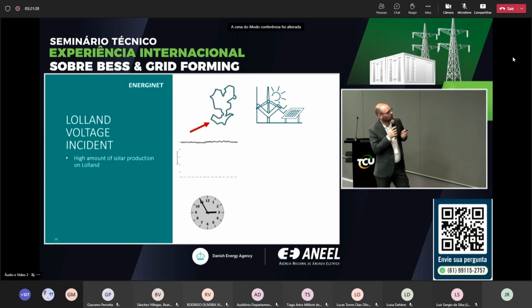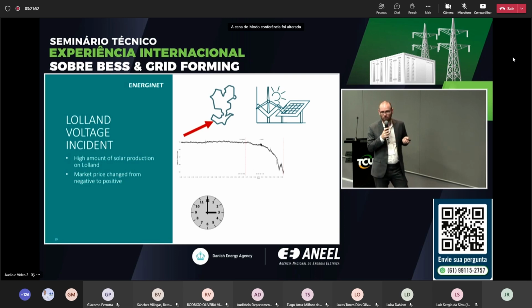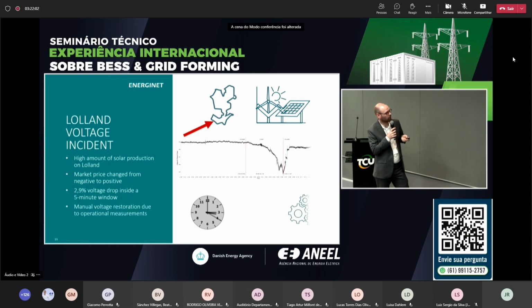Then we had an incident caused by a market price change from negative to positive, with a lot of solar and wind power suddenly turning on in a very short time, just when the hour switched. That caused a voltage drop of almost 3% in a 5-minute window, and that's obviously a challenge caused by inverter-based technologies, but also by market design, you could say.